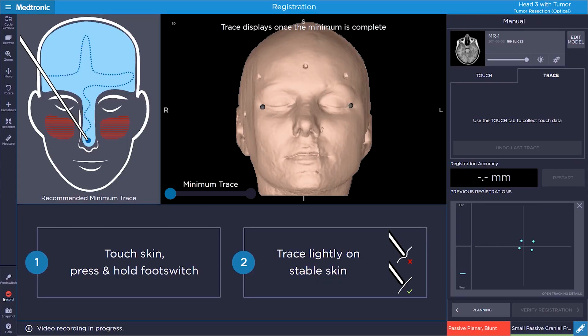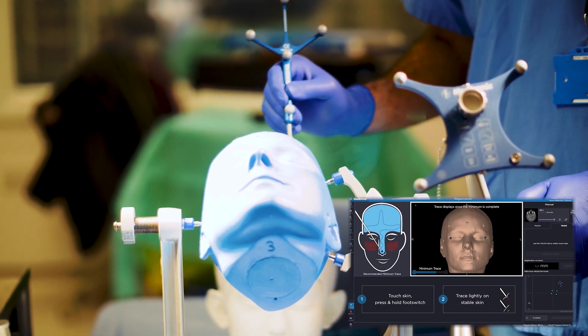In the bottom right-hand corner, we're using infrared tools and you can see the pointer coming into reference with the reference array that we've got fixed to the patient's head. We're going to be doing registration, marking out lots of points with the infrared pointer. Now we can verify the registration — we've got 1.5 millimetre accuracy, which we'll use for this simulation.